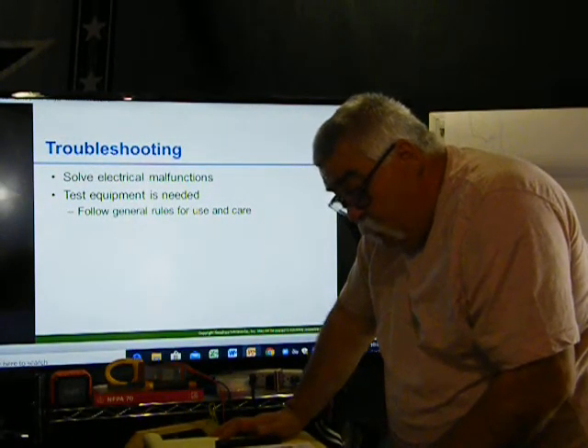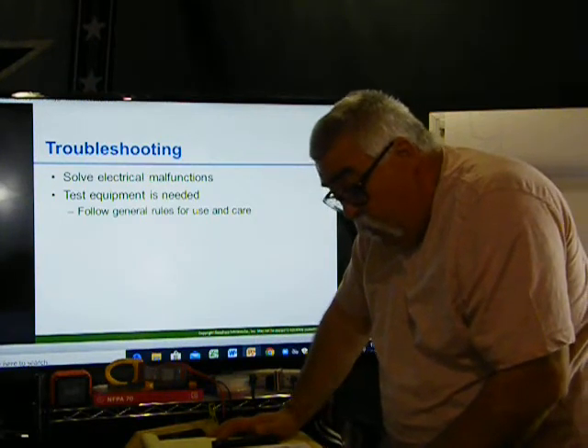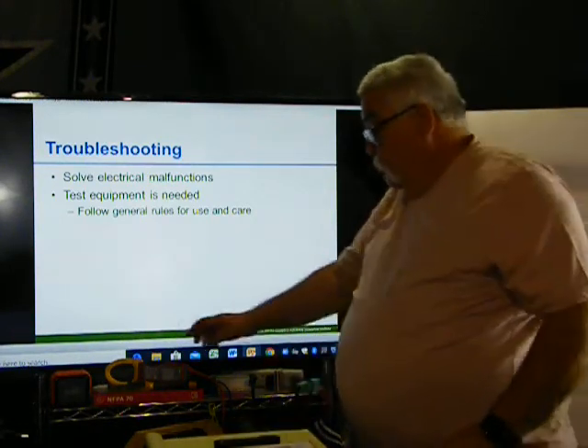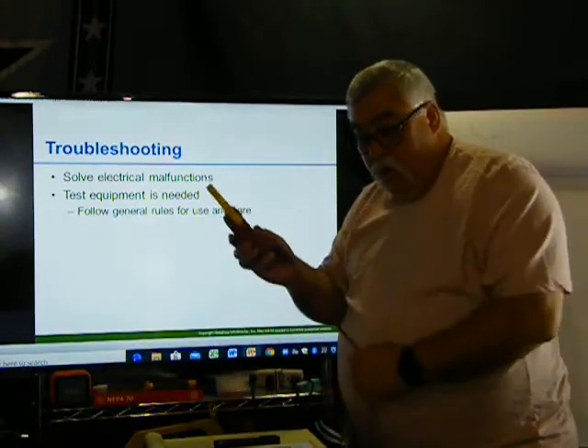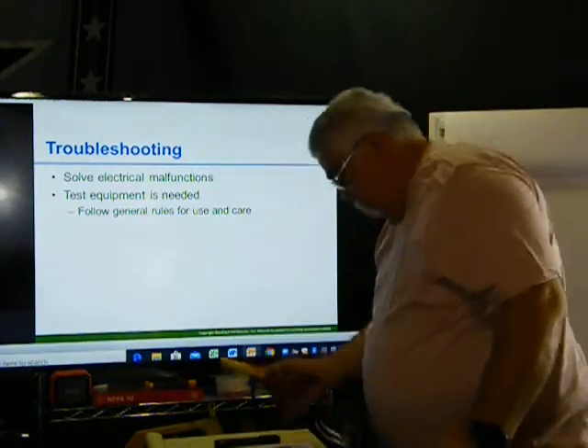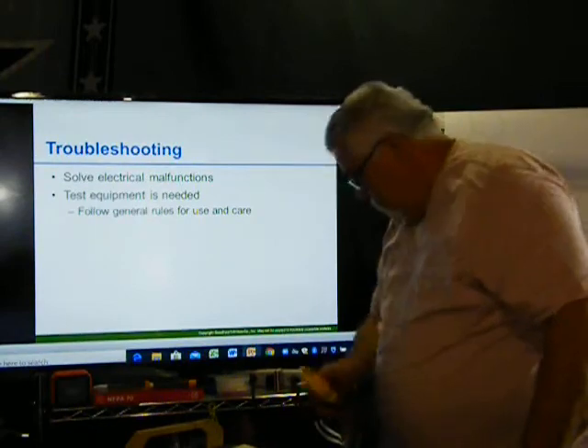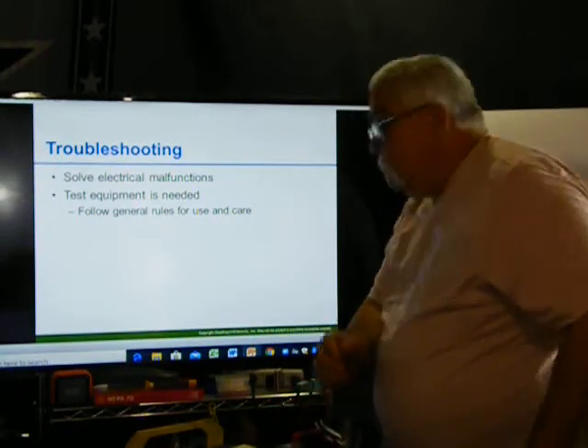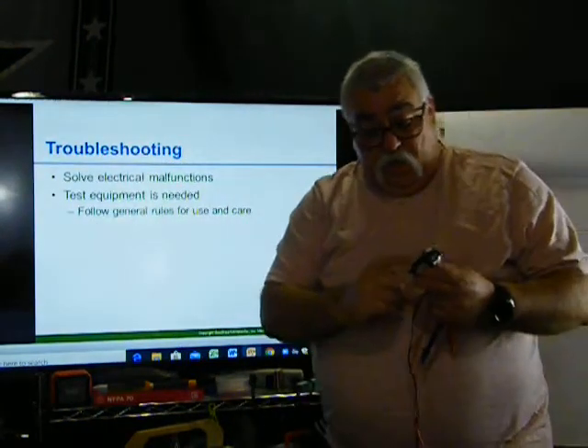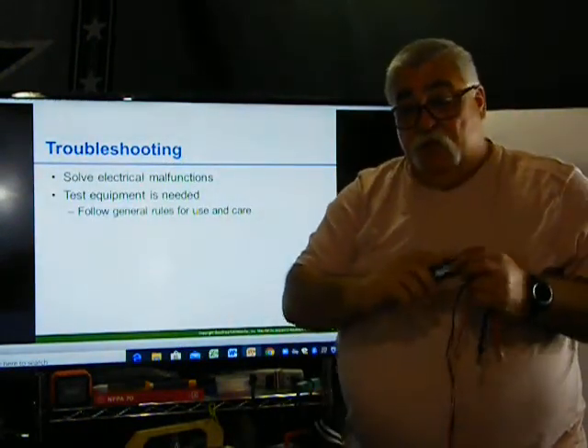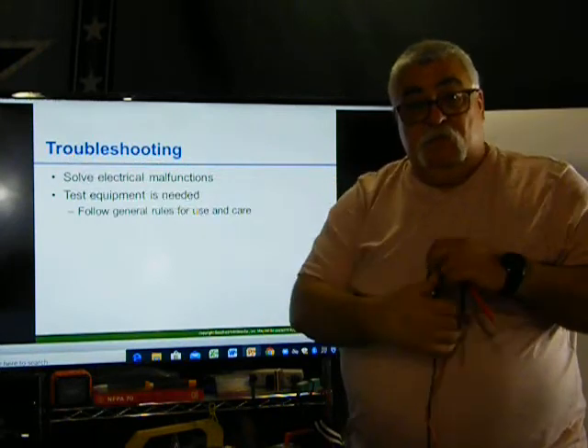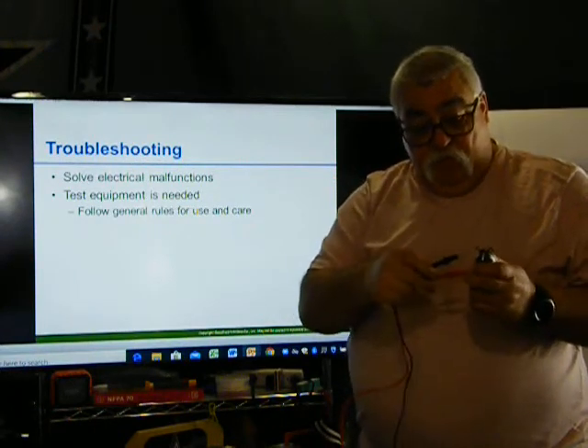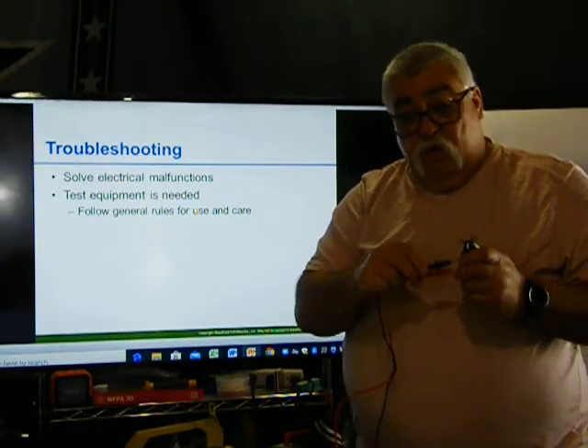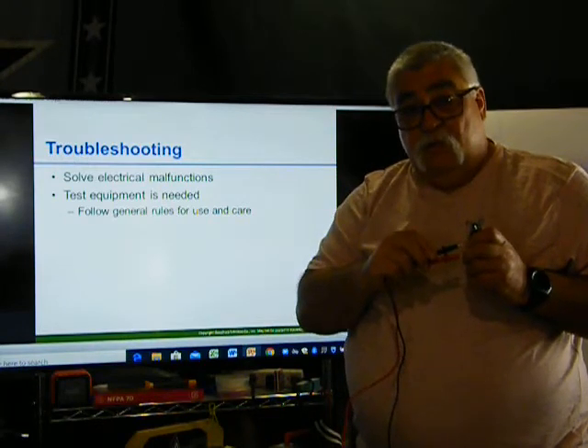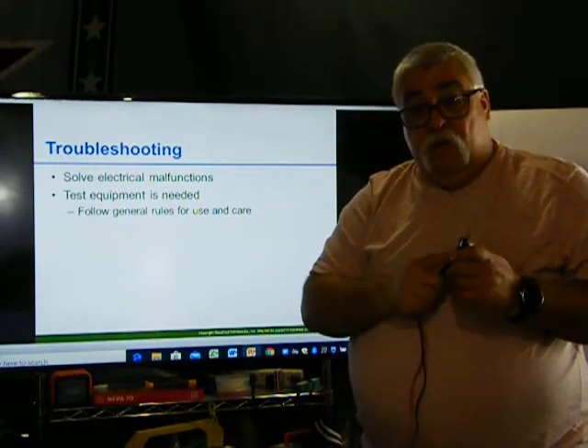When making resistance measurements, never work on an energized circuit. So when you're using this, and I'm testing, say, a receptacle, and I want to check if my wire is good between this outlet and the next outlet. Okay, so basically I'm going to go across here. The last thing you want to do when you're on the resistance test is have power on.